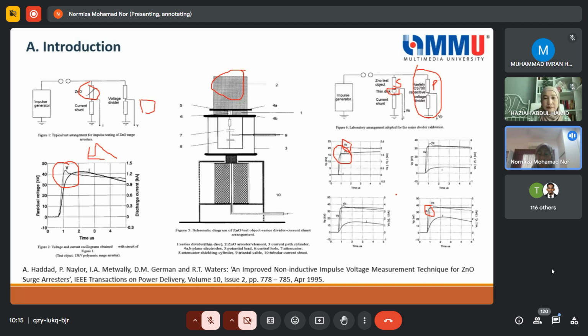But generally, we know that when we do the measurement, especially high voltage and high current measurement, the inductive effect can be present in our test circuit, which will give different results than what actually appear to be for the test loop. Okay, so this is one way to reduce the inductive effect. But as I mentioned, this is more for research purposes, but the common one is the second slide that I mentioned before.